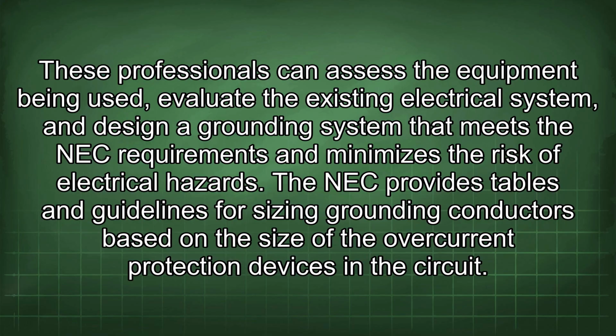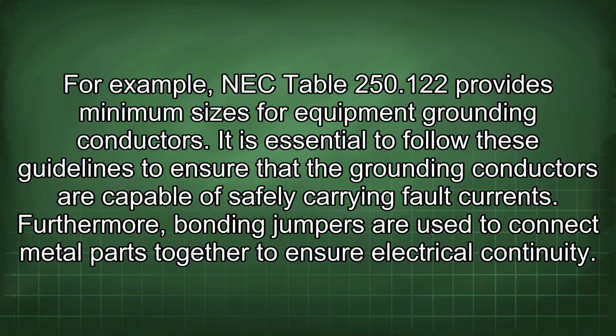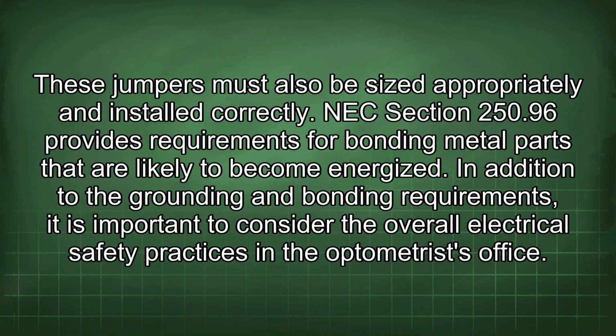The NEC provides tables and guidelines for sizing grounding conductors based on the size of the overcurrent protection devices in the circuit. For example, NEC Table 250.122 provides minimum sizes for equipment grounding conductors. It is essential to follow these guidelines to ensure that the grounding conductors are capable of safely carrying fault currents. Furthermore, bonding jumpers are used to connect metal parts together to ensure electrical continuity. These jumpers must also be sized appropriately and installed correctly.